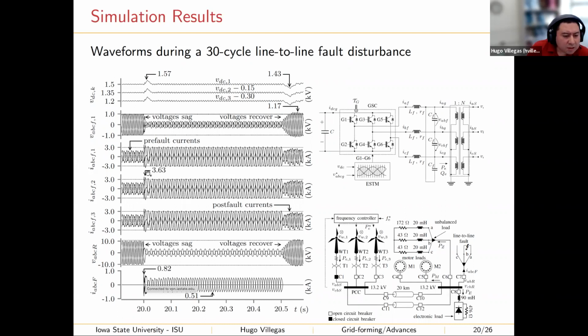During the fault, there is a slight spike, for example, in the current IF2, which is the current of the inductor that is at the terminals of the grid side converter. That current can go up to 3.6 kiloamperes. The Imax, the maximum limit that I'm setting up in the 2-axis anti-windup regulator, is 3 kiloamperes. Of course, the 3 kiloamperes is to bound the control set point, but there is no guarantee to bound the actual control variable. So it spikes to 3.63 and then returns to 3 and remains bounded within 3 kiloamperes.